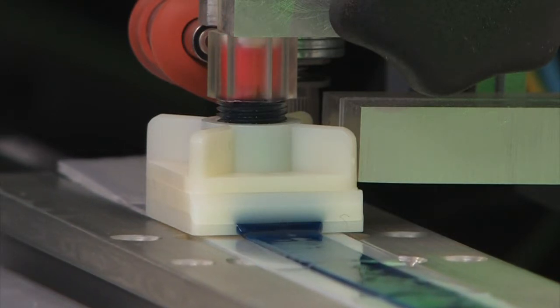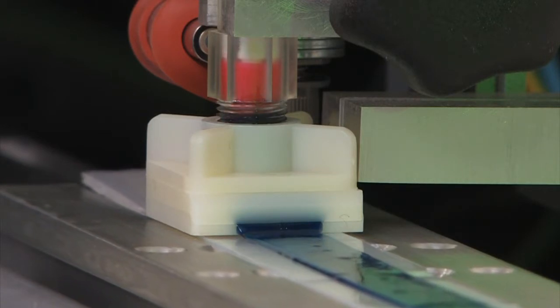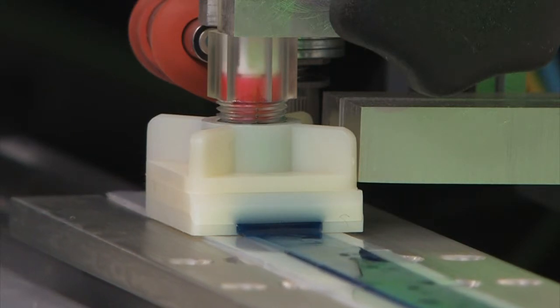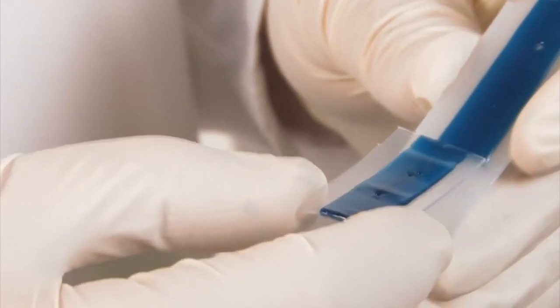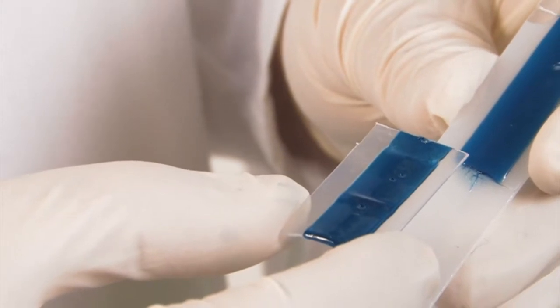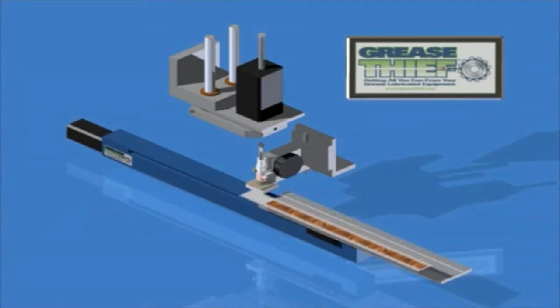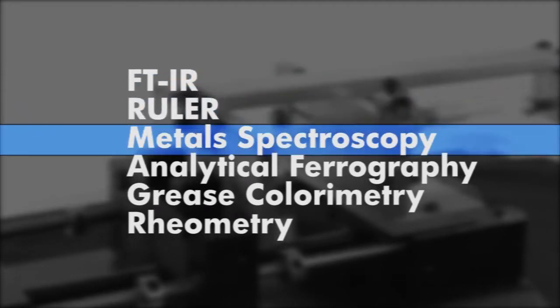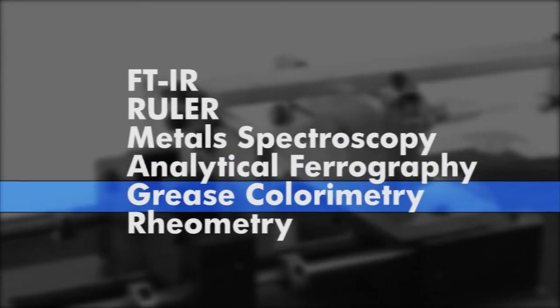In the final phase of the extrusion, the grease is squeezed through a 40-thousandths-inch-wide slot to create a uniform thin film that is deposited onto the specially designed substrate. The substrate has peel-away sections, each containing 0.25 grams of grease, which can be conveniently moved to other testing stations around the laboratory. Up to six other laboratory tests can be done with a single substrate, including FTIR, RULER, metal spectroscopy, analytical ferrography, grease colorimetry, and rheometry.